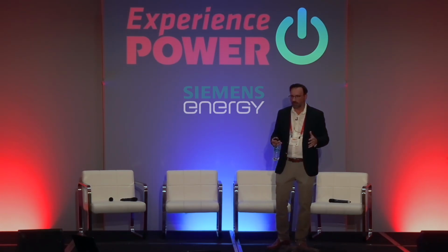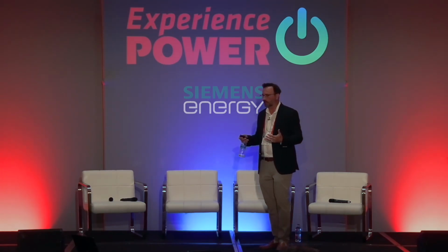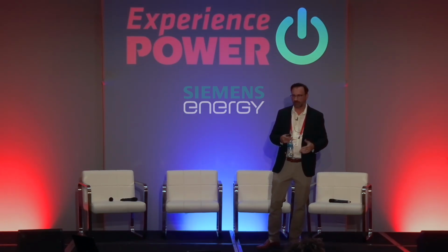Once you have that base model in place, this is where you want to start using machine learning techniques to further refine the model and get this model to perform very closely to the plant that is in focus, right, under all kinds of scenarios. So we need to go back and gather a lot of historical operating data. I would say at least a year's worth of historical operating data so that intrinsic within that data, you will be able to see how the plant performs differently under different weather conditions, under different operating modes. And the techniques used here will capture that information into the model, and that's very useful going forward for doing the simulations that we talked about, right?